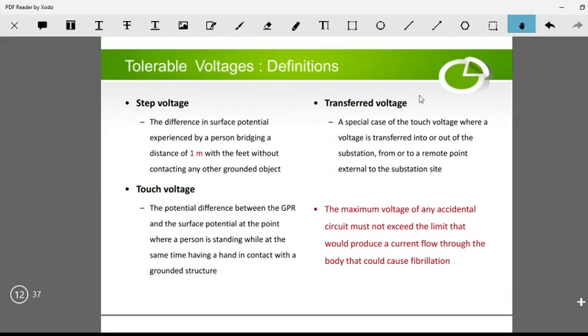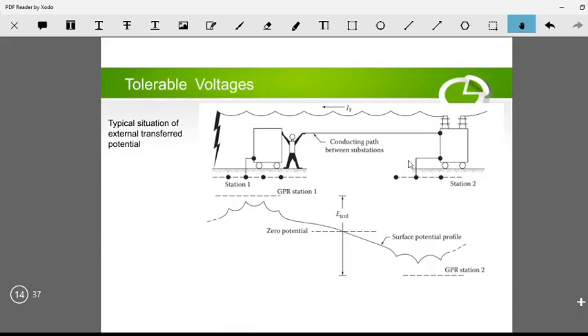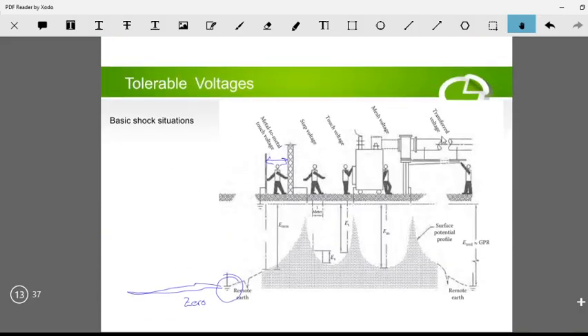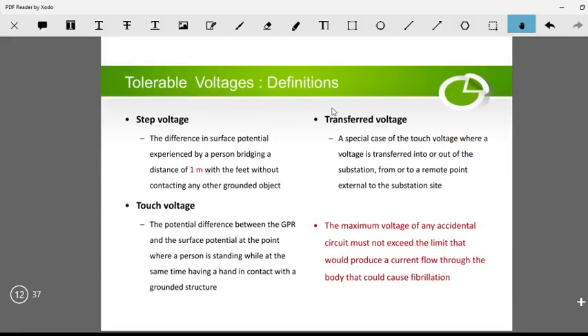Then you have something called the transferred voltage. The transferred voltage is defined as a special case of the touch voltage, where a voltage is transferred into or out of the substation from the site to a remote point external to the substation. So if you have outgoing conductors in the substation, and you accidentally touch something, there is a voltage generated at that point, which is known as the transferred voltage.